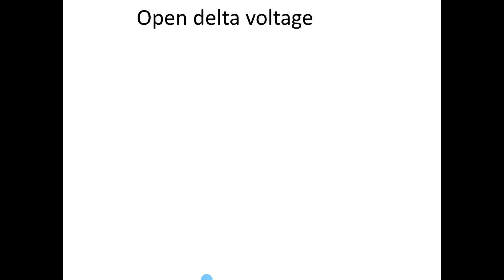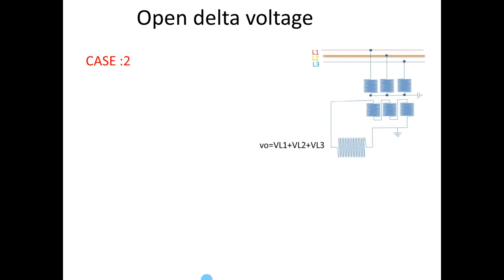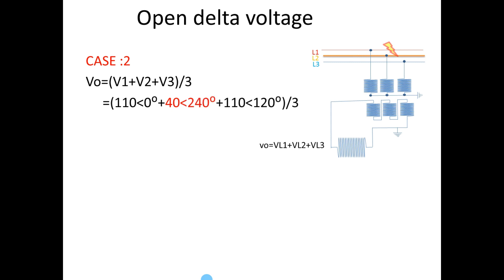Now I go for Case 2. Let us consider the fault on Y phase. During this time, depending on the fault current, the voltage will be dropped on Y phase. Let us consider the voltage on Y phase is 40V. The open delta voltage will be 23.3V at 60 degrees.